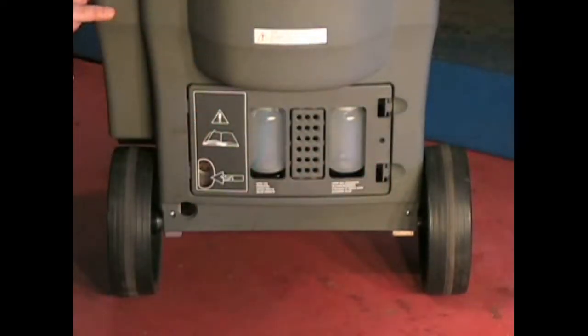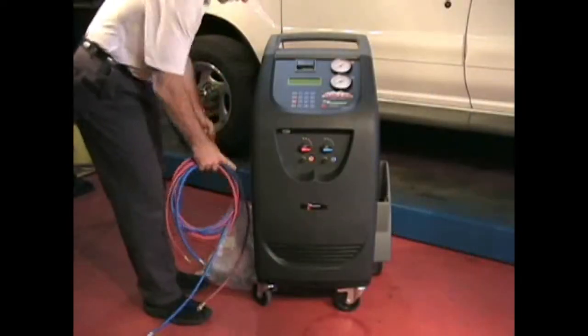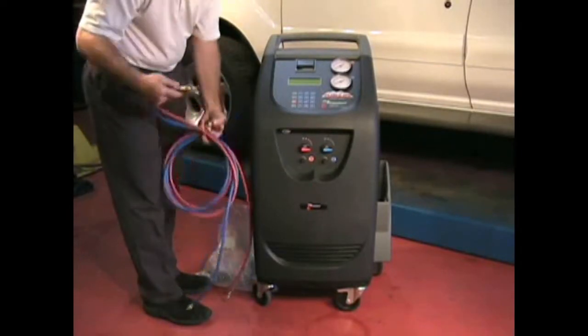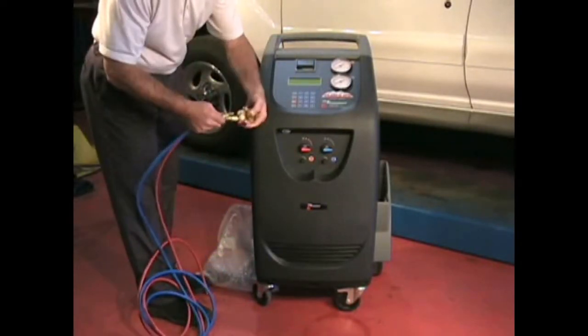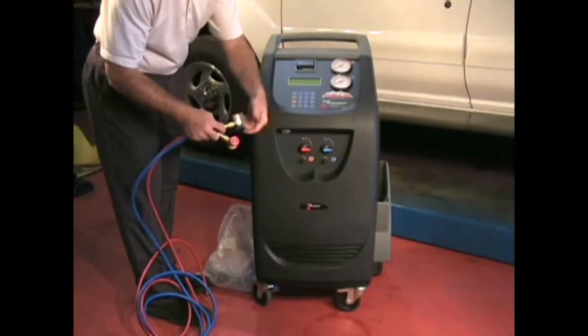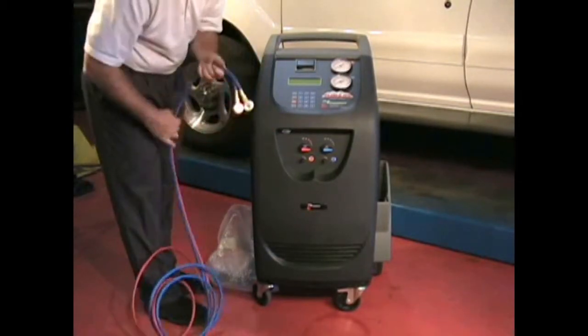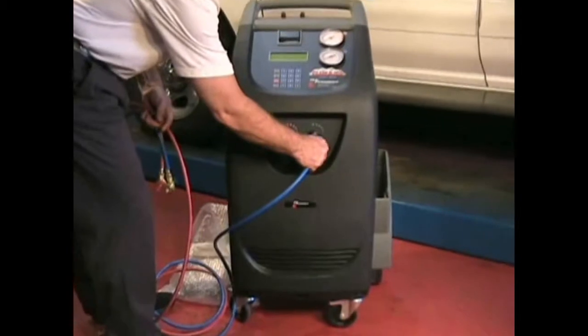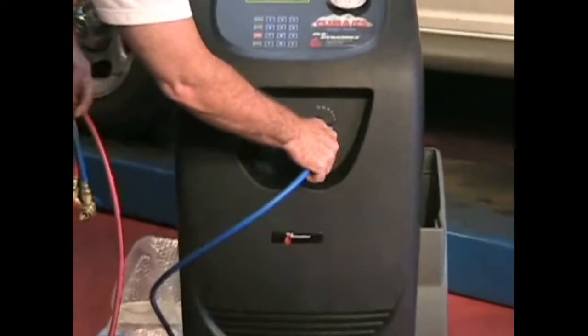Leave the pin in place to be reinserted in case the unit needs to be transported or rolled over very rough surfaces. Next, connect the high and low side service couplings to the service hoses, red on red, blue on the blue hose, and connect to the appropriate port on the front of the machine.